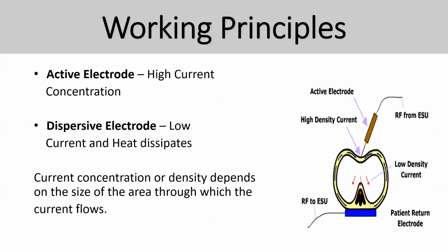Anyhow, guys, if you got any question, you can stop me. I can answer your questions on certain parts of it, or we can do it after the presentation. Okay, so when you talk about the working principle, the active electrode has high current concentration that goes through the pencil of the monopolar, and the dispersive electrode is basically low current, heat dissipation. So basically it's going to go through your body and through the patient return electrode. So the current concentration density depends on the size of the area through which the current will flow.